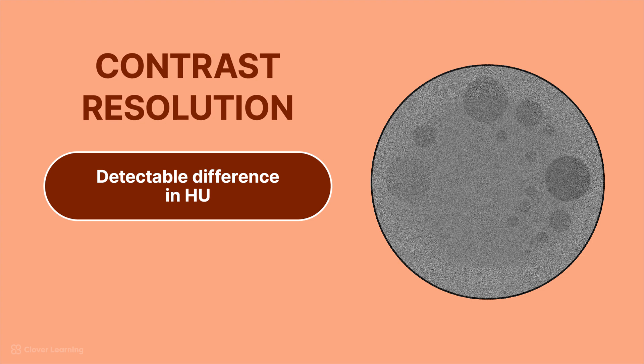Basically, the contrast resolution phantom uses a base material that's usually some type of polymer or something similar to water. And then it includes several areas with different size spheres that each have their own difference in Hounsfield units. Each area represents a different level of physical contrast.